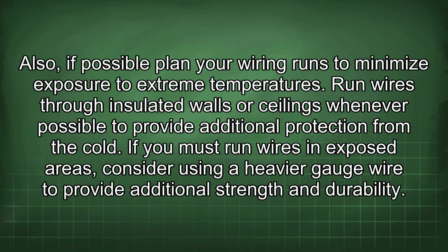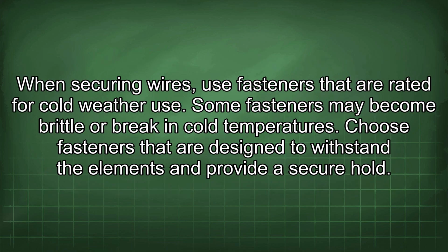Also, if possible, plan your wiring runs to minimize exposure to extreme temperatures. Run wires through insulated walls or ceilings whenever possible to provide additional protection from the cold. If you must run wires in exposed areas, consider using a heavy gauge wire to provide additional strength and durability. When securing wires, use fasteners that are rated for cold weather use. Some fasteners may become brittle or break in cold temperatures. Choose fasteners that are designed to withstand the elements and provide a secure hold.